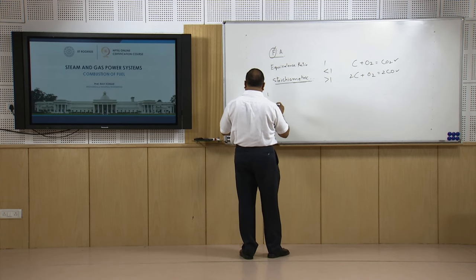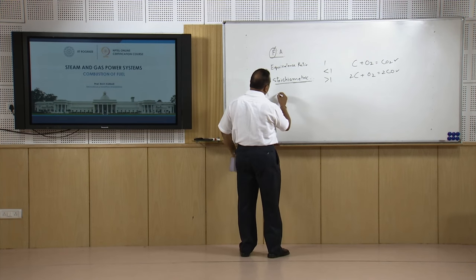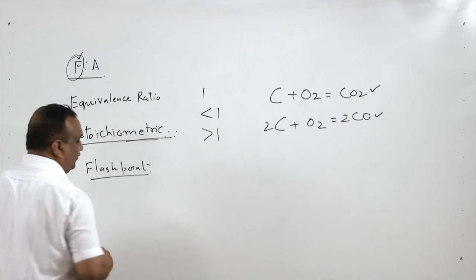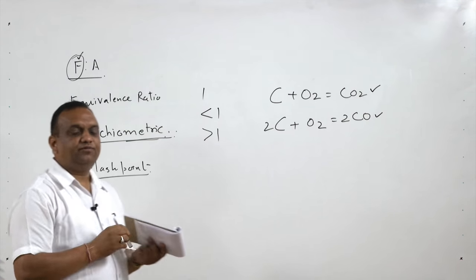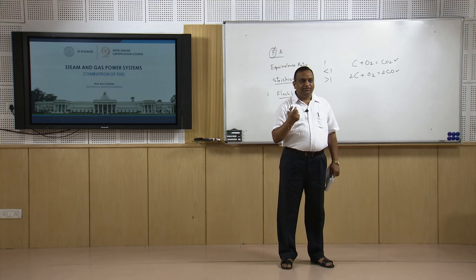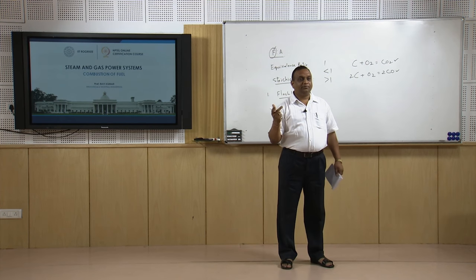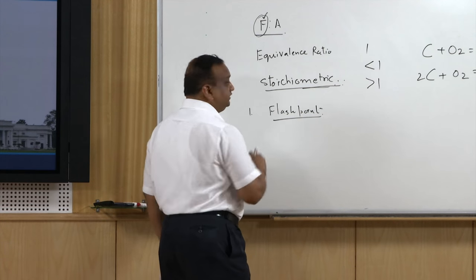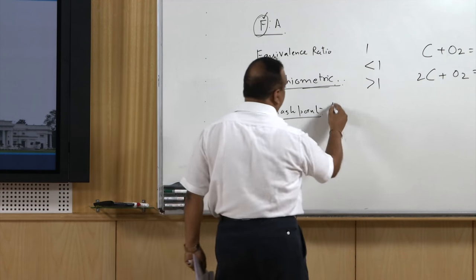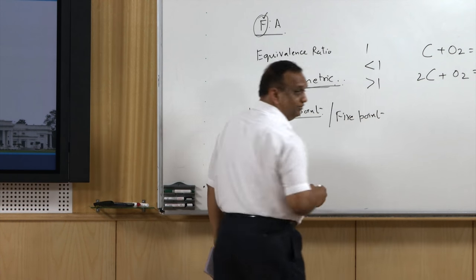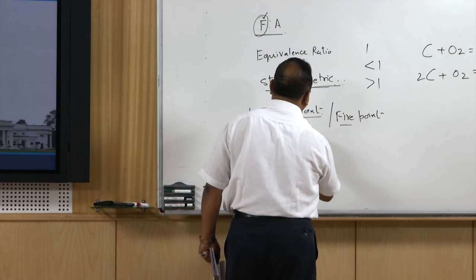Another characteristic of the fuel is flash point. Flash point is the temperature at which, if we start increasing the temperature of the fuel, vapors are generated — these vapors are volatile. An initial spark burns the vapor, but combustion is not sustained at the flash point. In fire point, combustion is sustained. So fire point is definitely higher than the flash point.